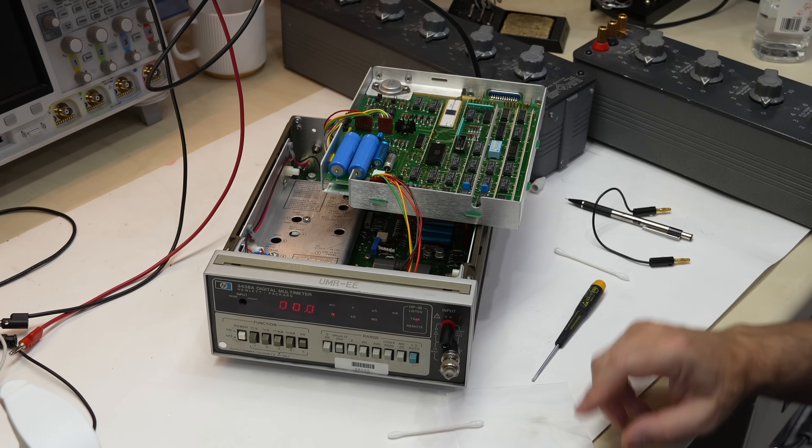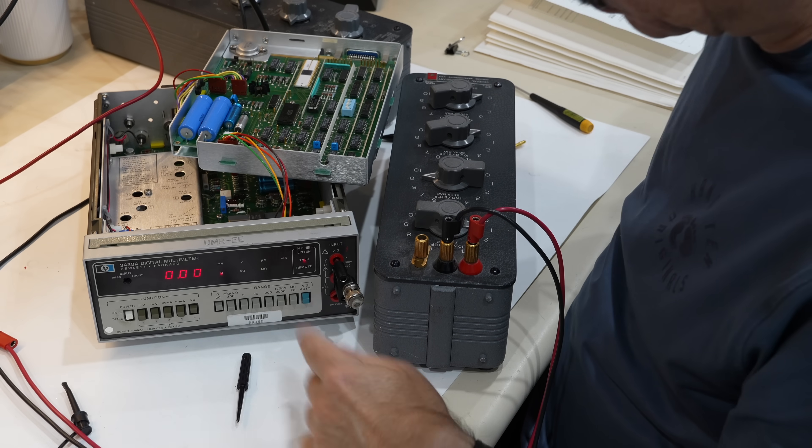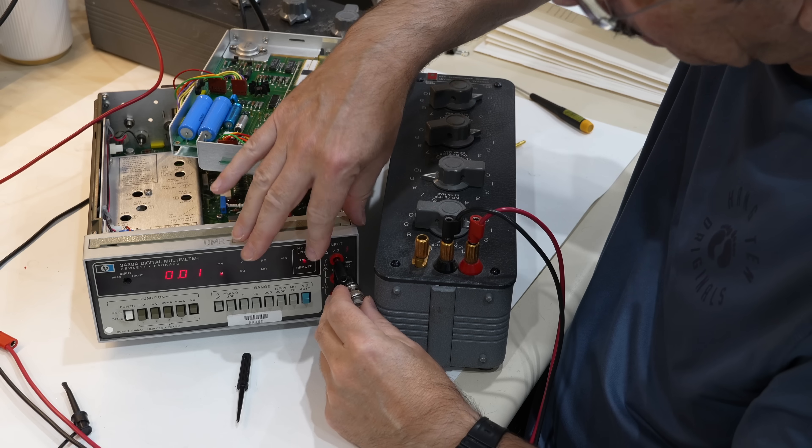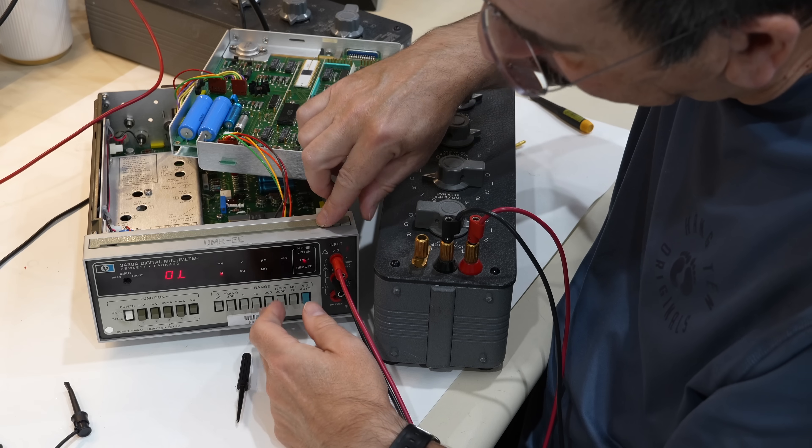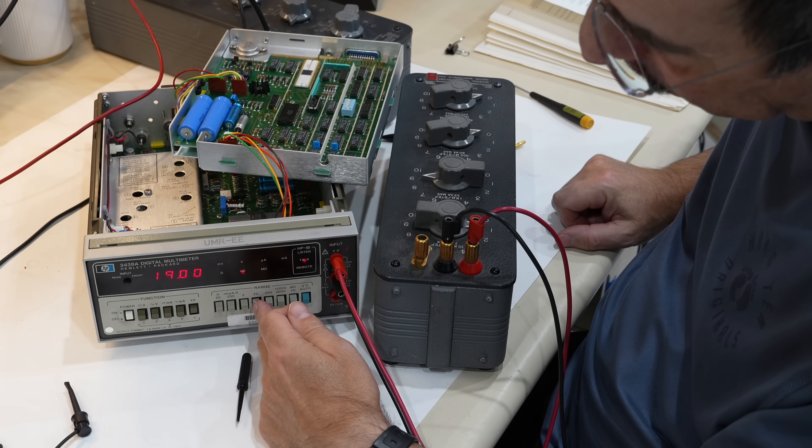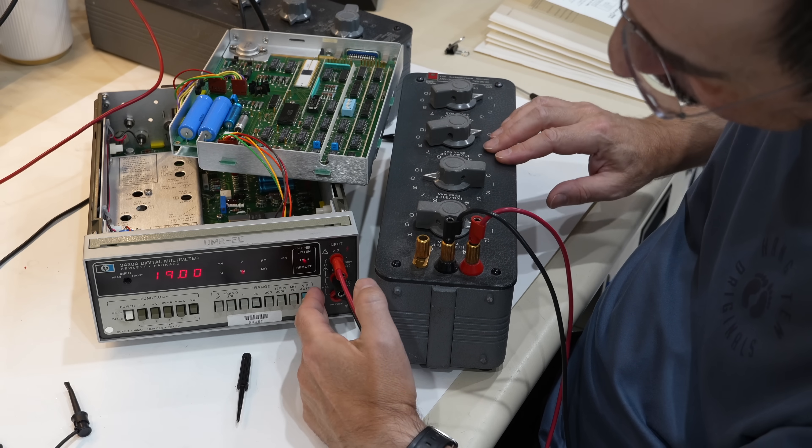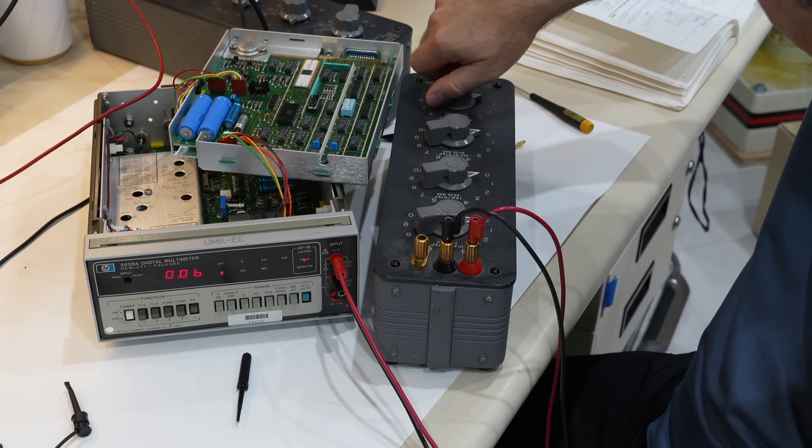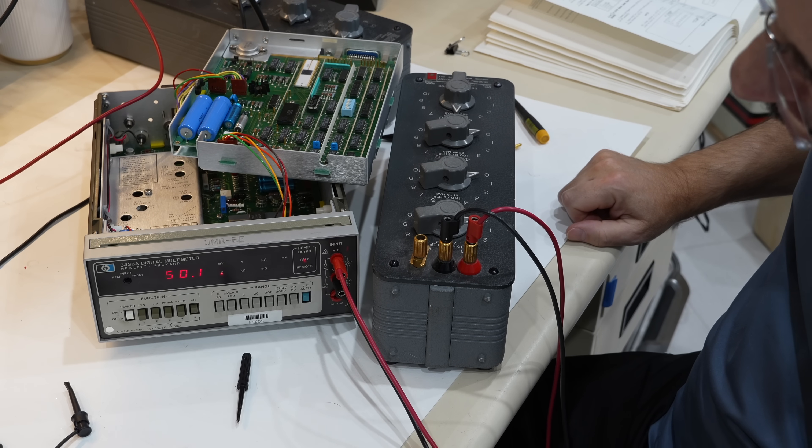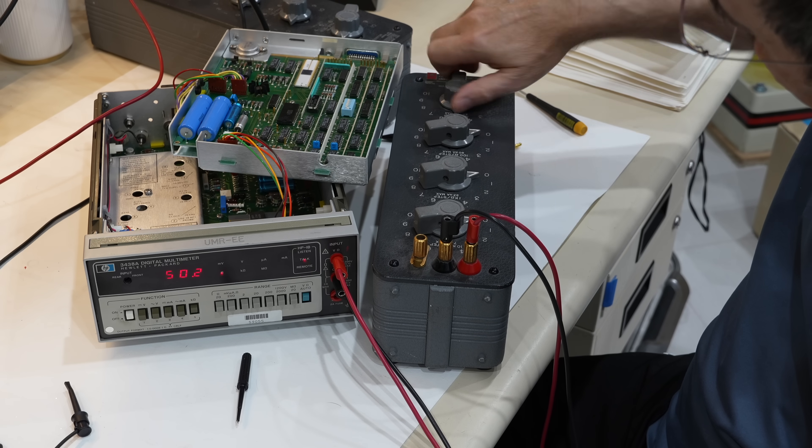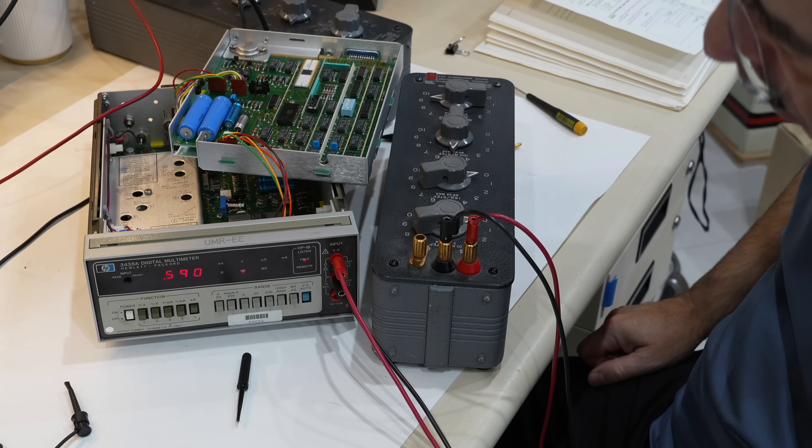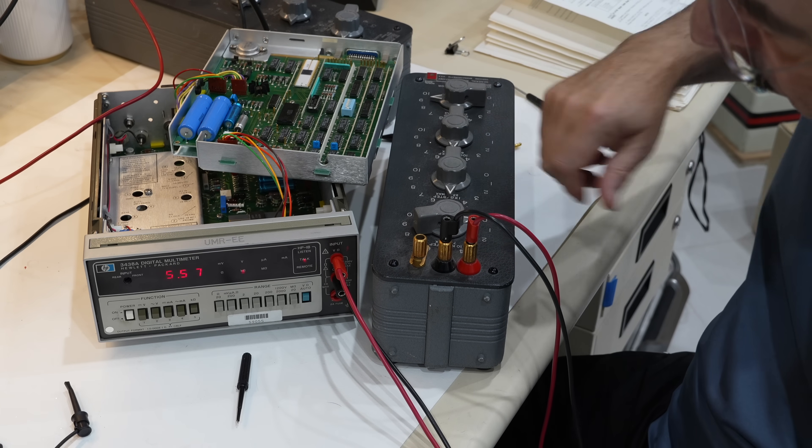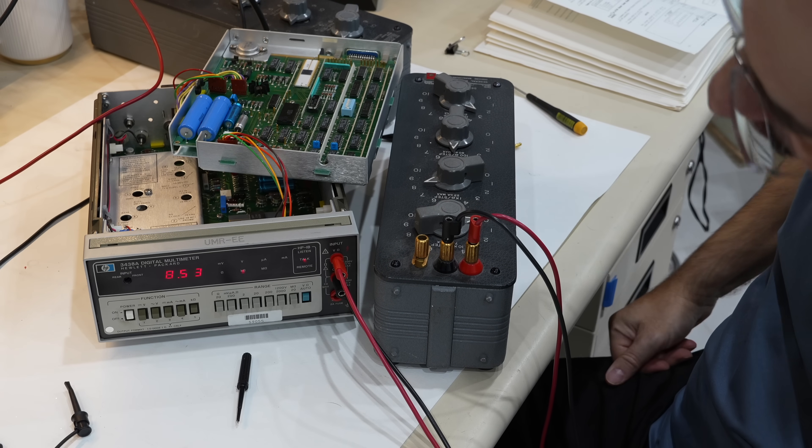Let's see what they say in the manual, but I think I'm correct. Okay, so experience proves that doing it the way the manual says is the best. So reading zero ohm to correct everything at the plug, and then adjusting it for 19 at the 19k. And then now I'm getting, if I get into auto range, I get good results. So we'll start with something really low, like let's say 50 ohms. It's 50.1 because it's the cabling. And then, well, let's get it to change range. 59, 590. Then we'll go to 8.53. There you go.